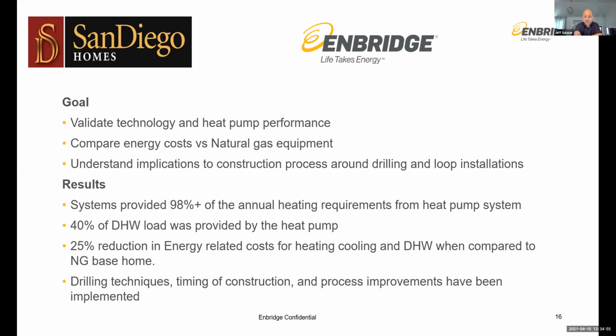One of the bonuses of these systems is the de-superheater functionality we added, which allowed them to produce 40% of the domestic hot water load for the season. That's a byproduct of the refrigeration process — I wouldn't call it 100% free, but during heating or cooling operation, the heat pump rejects excess energy from the refrigeration process and stores it in a preheat water tank, limiting the time the delivery tank needs to produce that energy. 40% was exceptional.